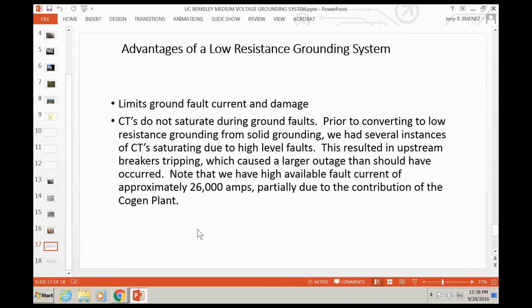So, next slide. There are some advantages of the low resistance grounding system, and there's really only two that I can think of, and this is a biggie. It limits the ground fault current and damage. If you have 1,000 amps of controlled current, versus on our campus we've got 26,000 amps of available fault current, that's a three-phase fault current RMS, that's a heck of a lot less damage. The damage goes by the square of the current, so we're talking 1,000 versus 26,000. The damage on a ground fault is minuscule compared to what we have on a phase-to-phase fault.